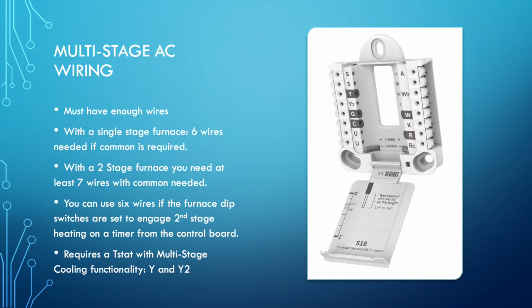If it's somebody doing an estimate to sell a system, take a look. Are we going to have to run new thermostat wiring in order to achieve what the customer is asking for? Even when you're going into furnaces that have only two wires because they've never had cooling before, you've got a problem with the number of wires, in which case we're looking at using a wireless RedLink system that's going to need an EIM board at the furnace and a secondary transformer to power that EIM board for wireless connectivity, in which case then they can have all the wires they need.